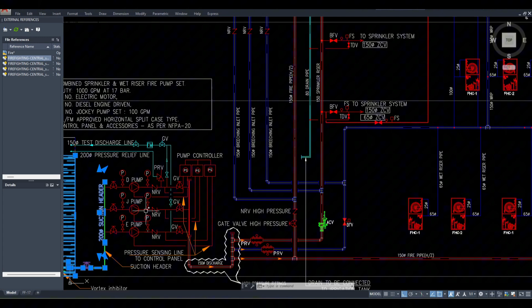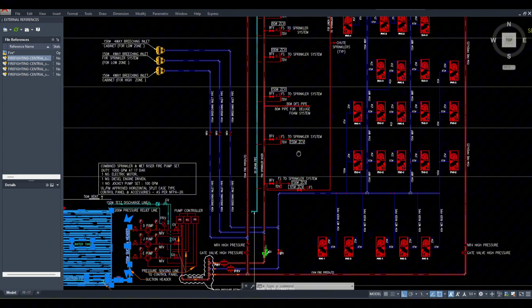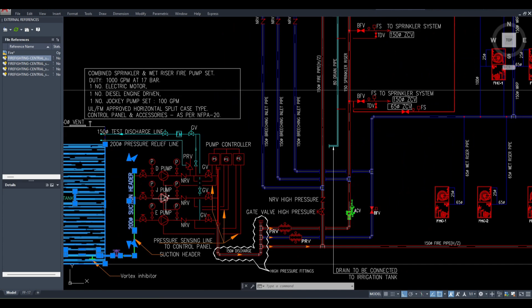then what will happen, then this electrical pump will start, this will trigger. Okay, so all these things are programmed in such a way that they will work back to back. Electrical pump will start with a bigger capacity than this jockey pump, so it can maintain the pressure as well. So what it means, once the electrical pump is starting, it means the real fire is there somewhere. Okay, and more water demand is there, that's why the jockey pump is not able to maintain the pressure of the line, so that's why the electrical pump has started now. After that, the electrical pump will take care of all the demands and it can maintain the pressure as well as the flow rate.